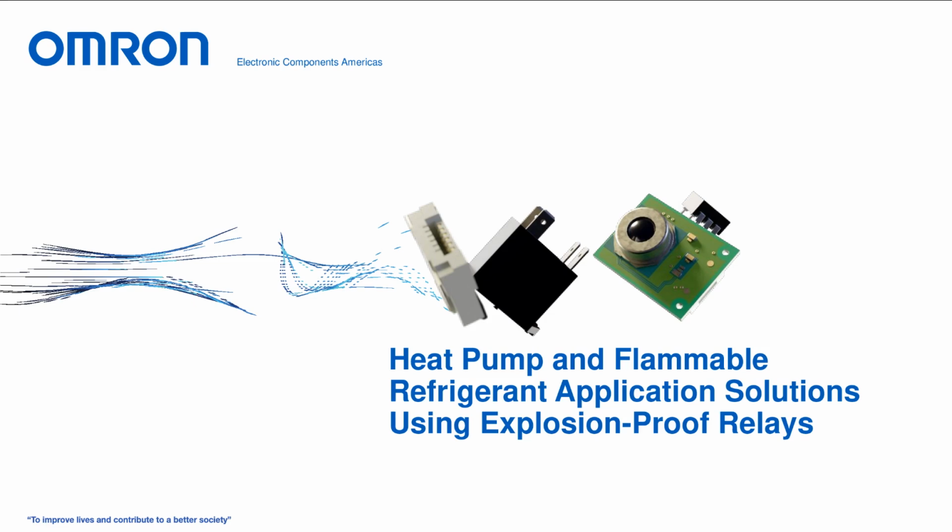So this is where we get into how we attain the certification for 16 amp and below switching. We do have unsealed versions, unsealed products that are certified. They are flux protected, unsealed products that are certified as explosion proof. And once they're certified as such, they're no longer an ignition source.